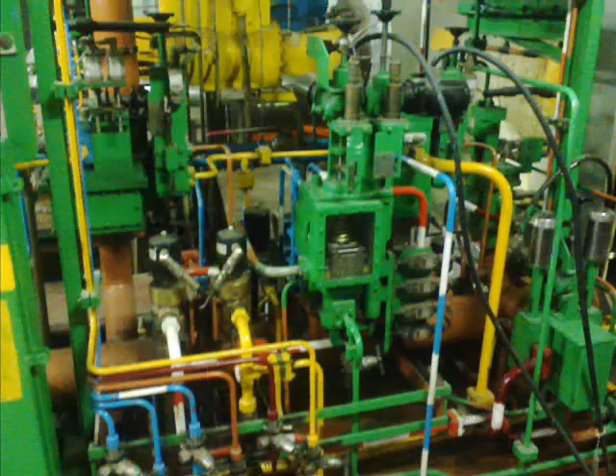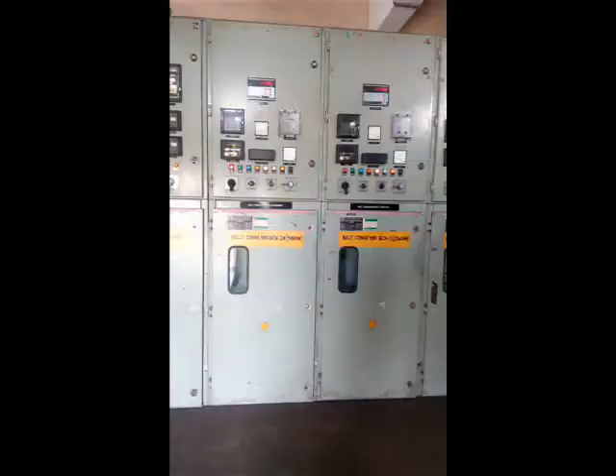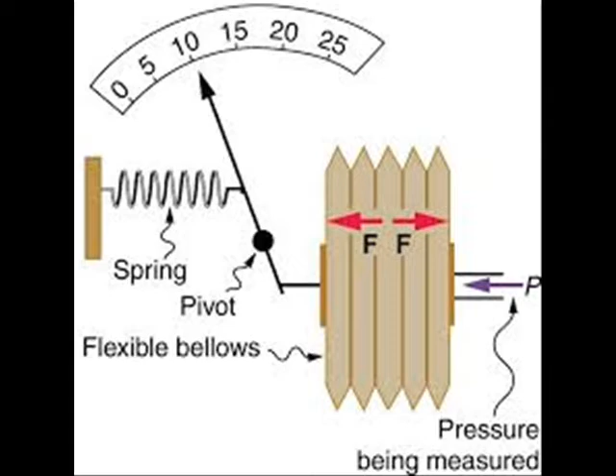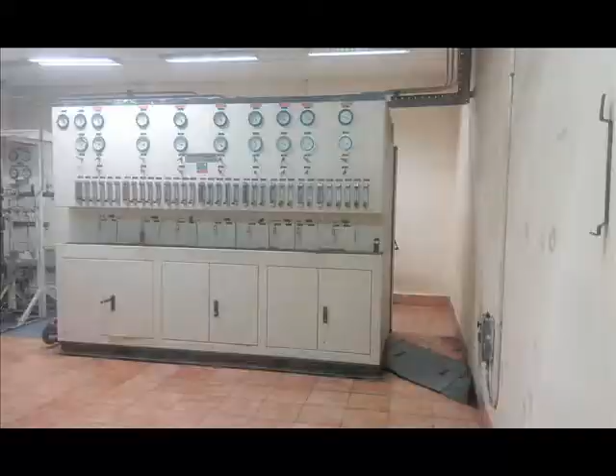The main work of an instrumentation engineer is testing, fault analysis, and commissioning of the turbine control system and plant DCS systems, like boiler and BOP, and also control valves, motor-operated valves, solenoid valves, electrical breakers, servos, PLC, and SCADA testing, such as RO/DM process, ash handling plant, PT plant, jackwell pump house, and so on. Calibration and replacement of plant field instruments, as and when required. Testing and calibration of plant measurement circuits: pressure, temperature, flow, speed, position, and vibration probes. Testing and commissioning of plant analyzers like pH, silica, conductivity, phosphate, SOx, NOx, CO, dust emission, and oxygen analyzers.